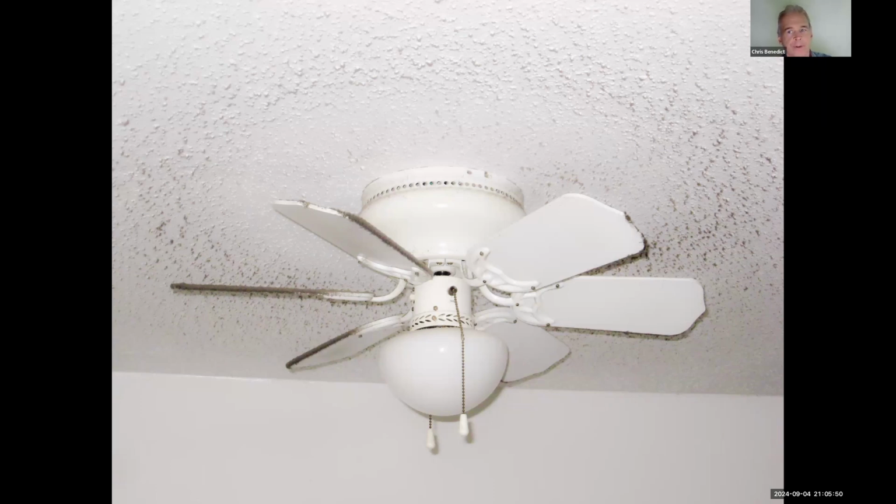Yeah, so if you have a crack on a door and you double the pressure drop between indoors and out, rough numbers, you'll double the air leakage. And if you have a hole and you double the pressure drop, you'll less than double the air leakage.